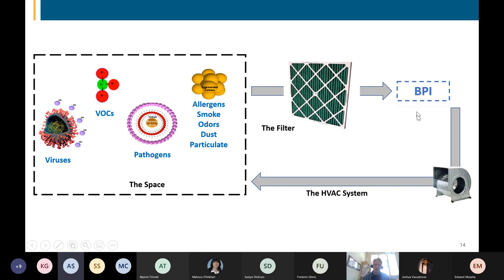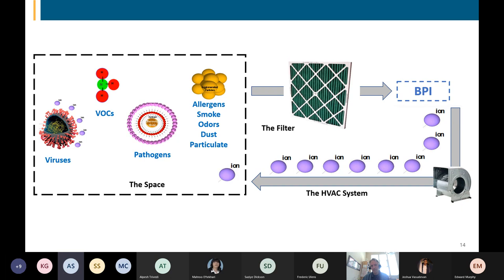I show a bipolar ionization technology installed in the HVAC system, emitting ionization, charging the air that goes over and through the device with a positive and negative ionization potential. Those ions then flow out through the ductwork, through the registers and grills, and mix with the room air itself. It's treating the air where it's suggested that we may need to treat it to be the most effective. And it then begins doing what it does on various contaminants of concern.